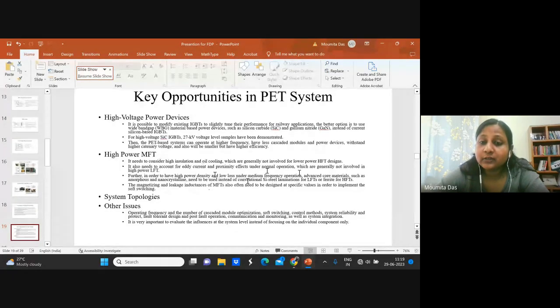Another important thing is the core material. In India it's very easy to get ferrite core, and silicon steel lamination is available for line frequency, but for high frequency mostly ferrite cores are used. For amorphous and nanocrystalline materials, we have to import from outside since we don't really have industry that can provide these things easily, even for lower power applications. So there are three different challenges: cooling mechanism, loss distribution at high frequency high power, and the core material - we probably have to go for different materials suitable for high frequency.